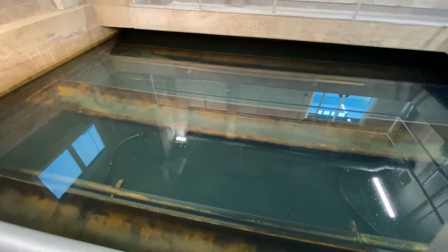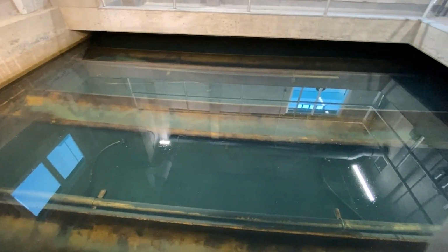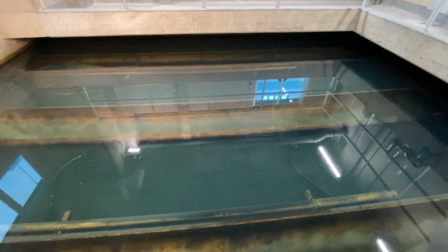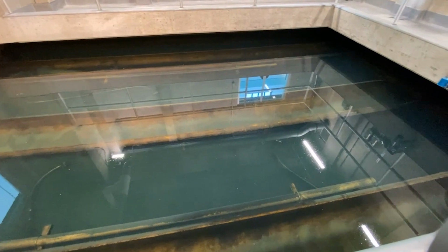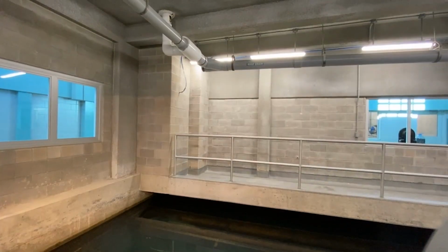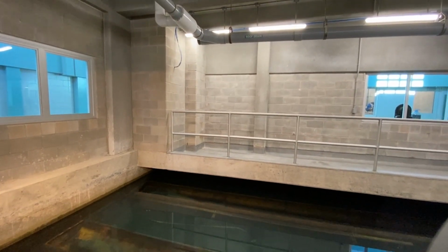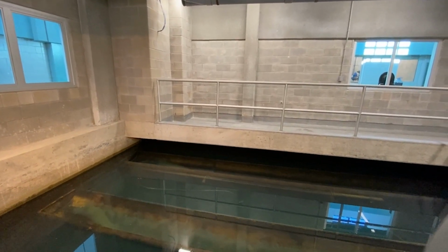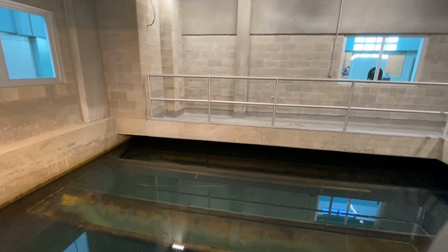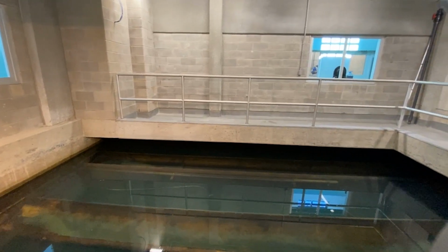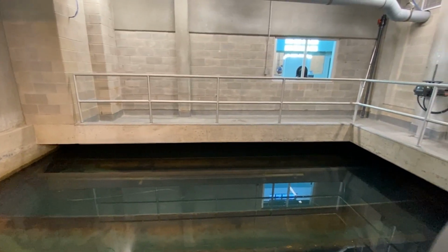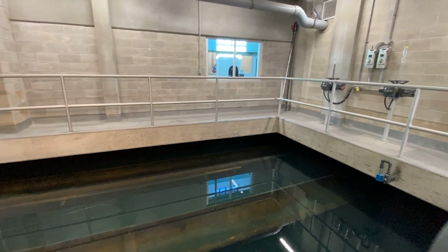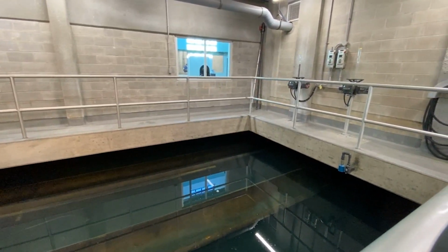Now it's time for filtration. At this point in the process, the water will appear to be clear. However, it still contains bacteria and various small suspended solids. To remove these contaminants, many water treatment plants will use sand filters. Sand filters are layers of different sized sand particles that filter the water through them. Some facilities even use activated charcoal filters, which are basically giant Brita filters.